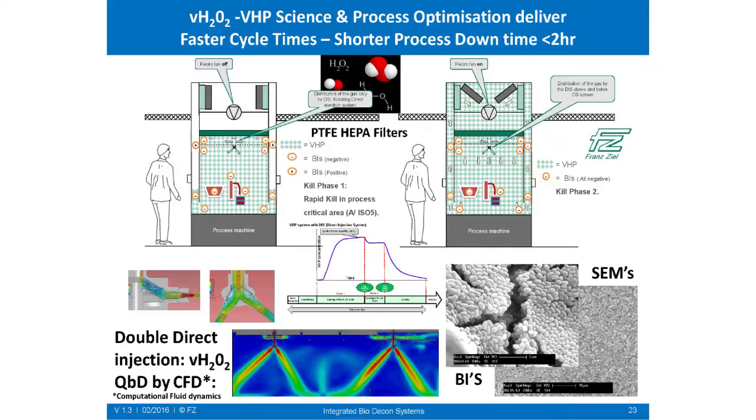Now, you can do sort of system d-value, enumeration checks, classical, but these SEMs do really reveal what the quality of the BI is. And my team of microbiologists, and the 4 of them in Germany, each of them have been trained to do SEM analysis at a local institute. Now, these SEM scan electron micrographs cost 1 or 2 million each, so there's not something you have on your bench. So you can go to their facility. But you can't send your BI to have it scanned by an analyst who doesn't know what he's looking at. So you need a microbiologist that knows what they're looking for and really target the BI and respond to what they're seeing.